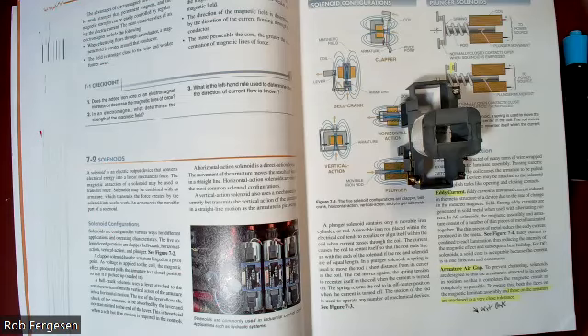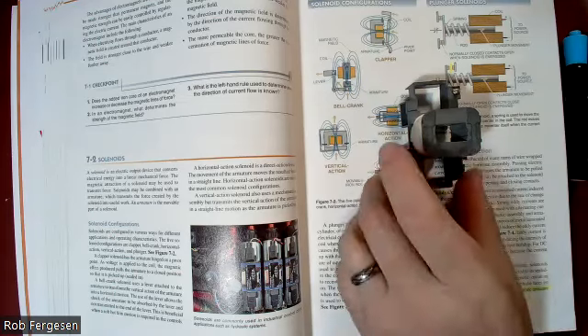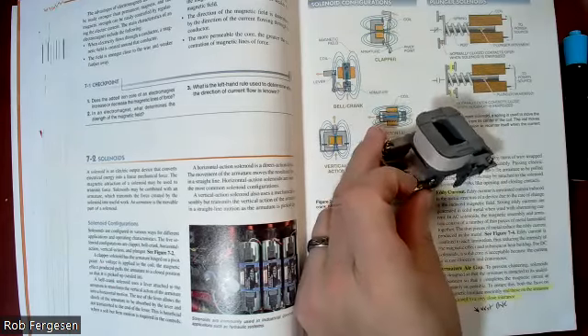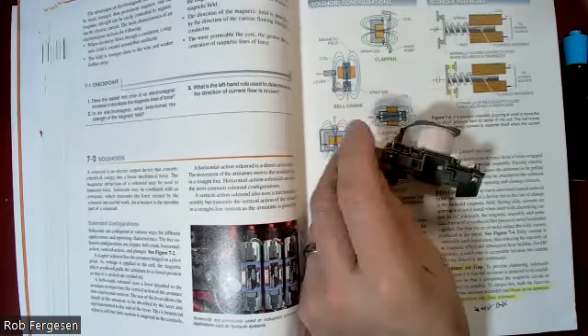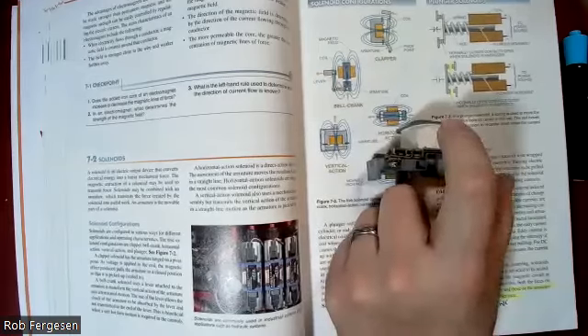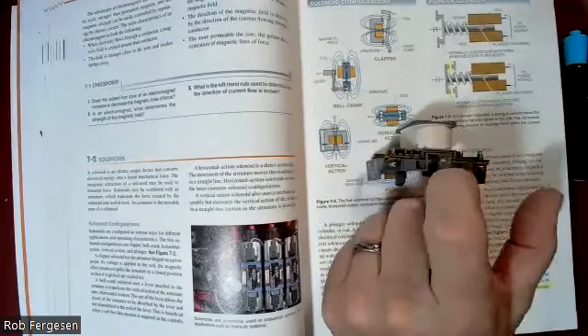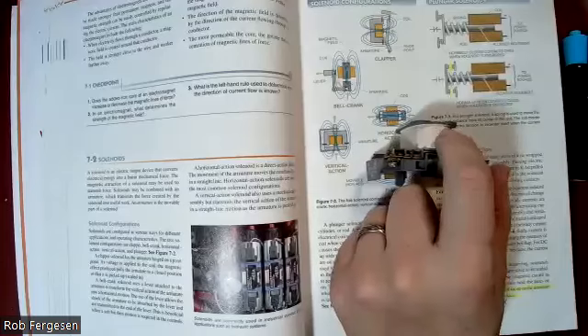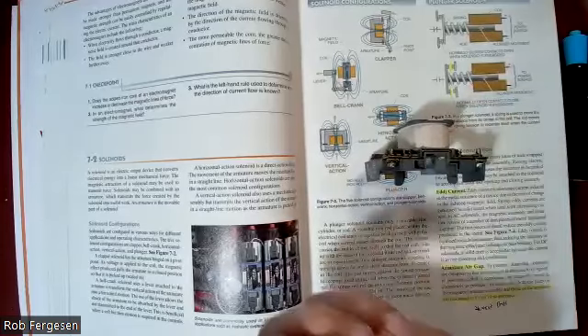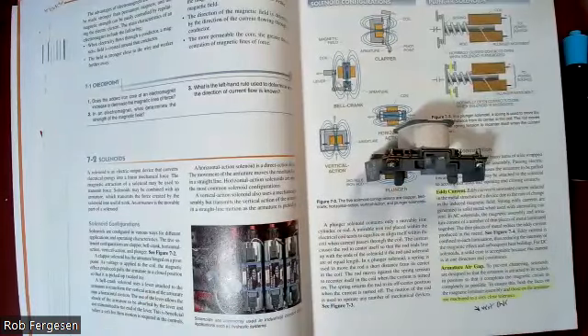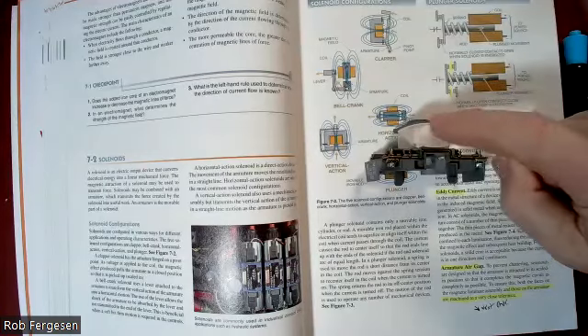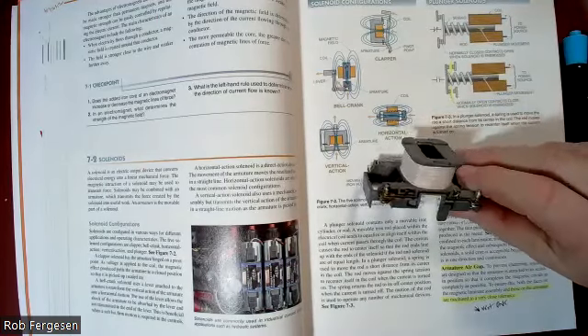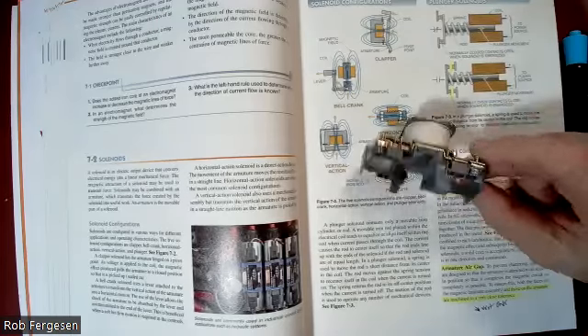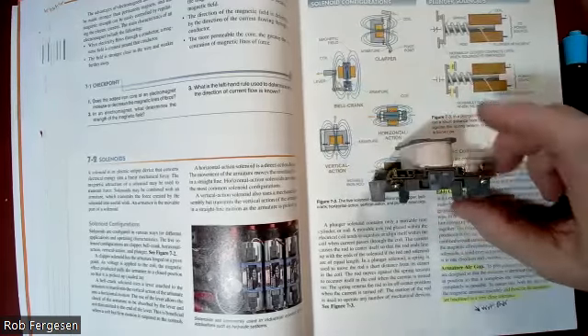Because one common failure point, for any kind of relay or contactor, is the coil. The coil itself is constantly being heated up and cooled down. Anytime you energize it, it slightly warms up. Anytime you de-energize it, it slightly cools down. And we're going to go into troubleshooting later on. Also, high voltage or low voltage can burn out a coil for different reasons.